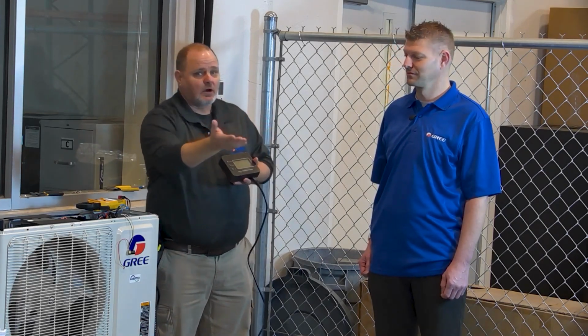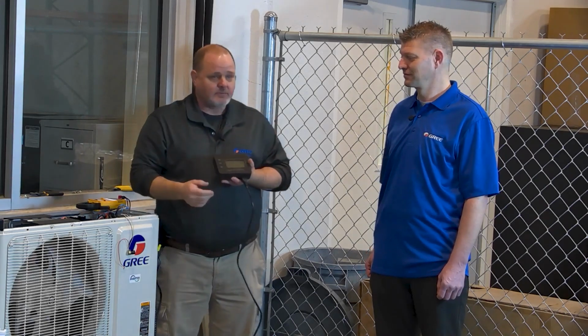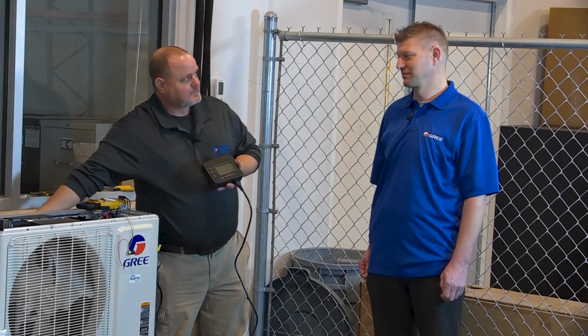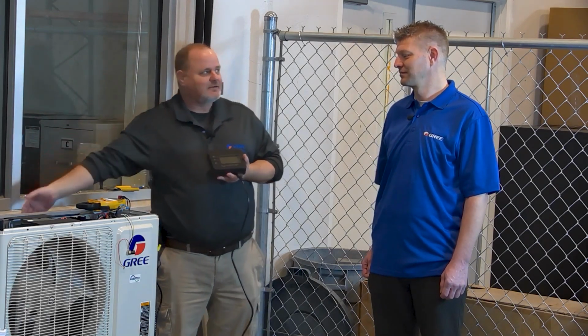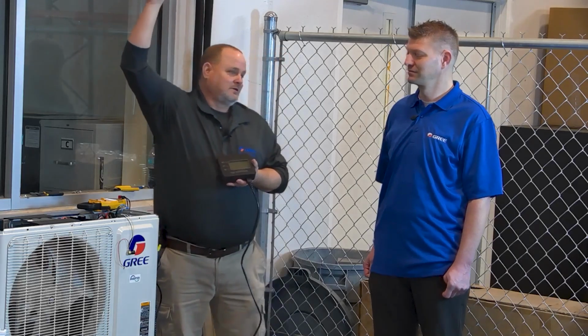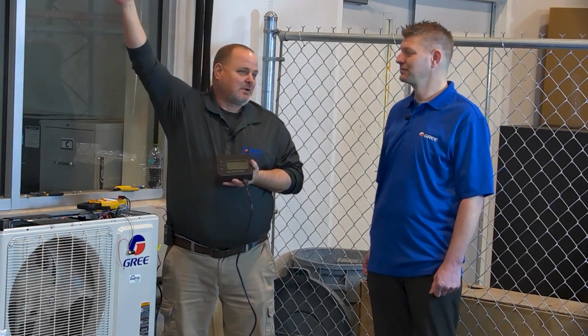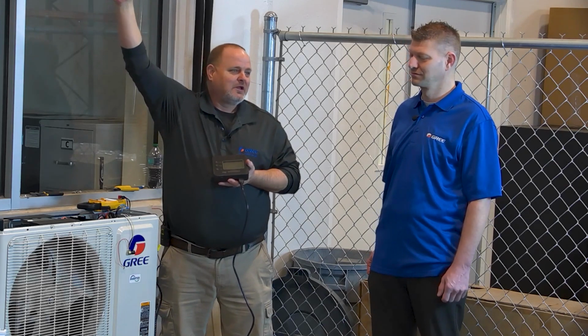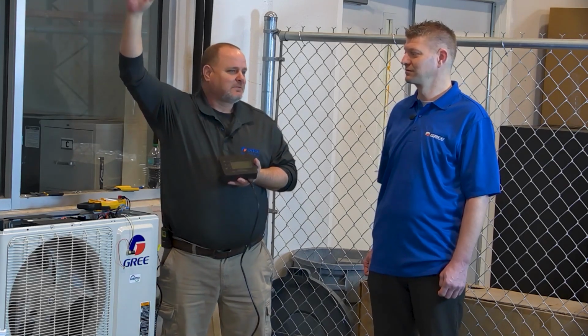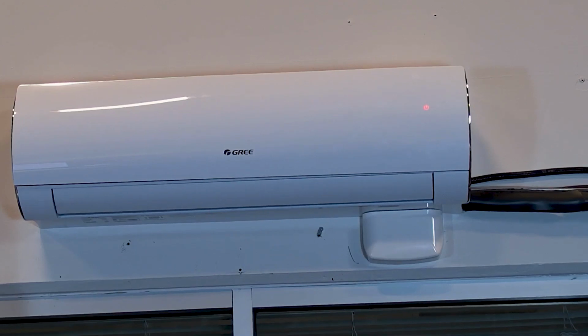This service tool will give you, as I was showing on the piping diagrams, a temperature thermistor on the condenser coil, right? Well, if I take that condensing temperature and convert it to pressure on a pressure temperature chart, then I know the head pressure, don't I? They give you a thermistor on the indoor coil. It's in the middle of that evaporator coil. So if I know the indoor coil temperature and I use a pressure temperature chart, I also know what my suction pressure is. Right? Yep.